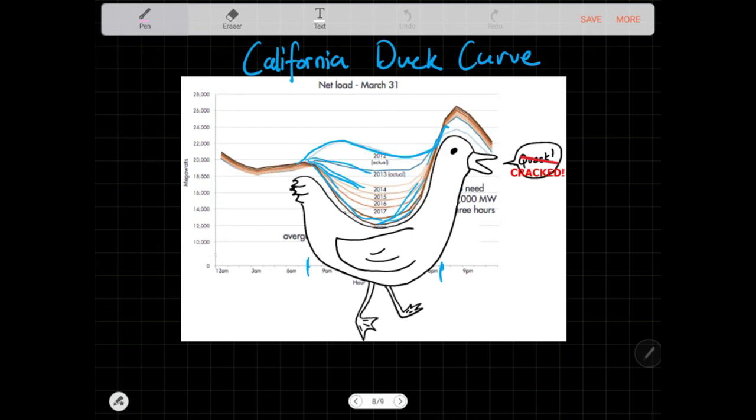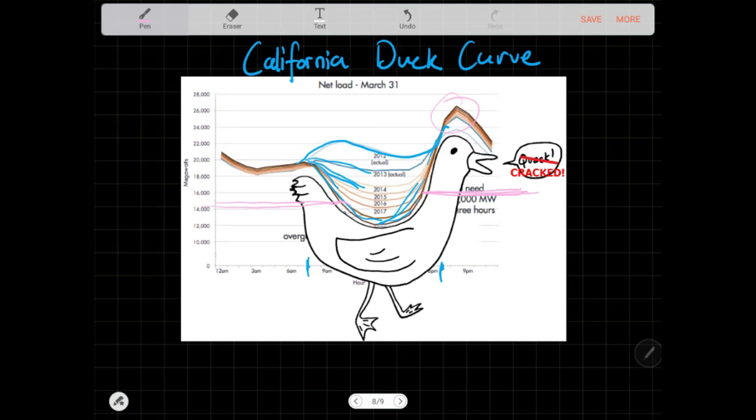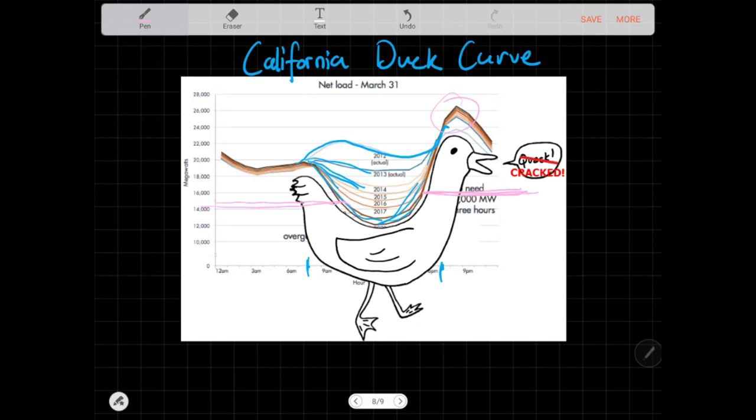I suspect this is a weekend curve where the demand is peaking in the evening, where the baseload plants do get shaved off. Here's the thing: baseload plants are very inflexible in the sense that they have a very small range of minimum and maximum operation. Asking them to be the regulatory unit where they are the ones going up and up and down actually causes more wear and tear to them because they're not designed for that. While combined cycle plants, they can go up and down their energy production very quickly. Nuclear and coal, they have a very low ramp rate. They cannot do that without much stress onto the machine.